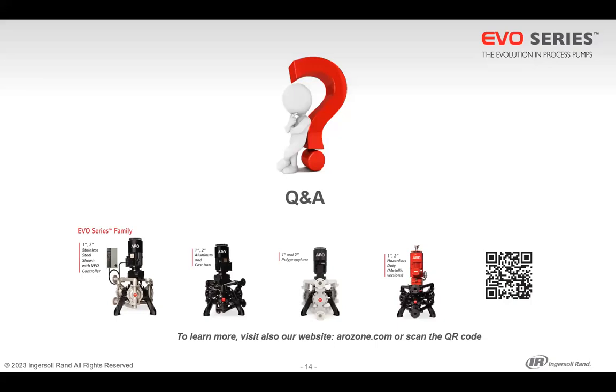Actually, in this application, the customer ran at 100% of torque for a while. Then I've been there and suggested they reduce it, but actually the test was going well even at 100% of torque. Simply they did not need it. And it's also much better for the system, in case the powder packs, not to have the full torque on the powder. But apart from that, I think that this answers more or less your question.